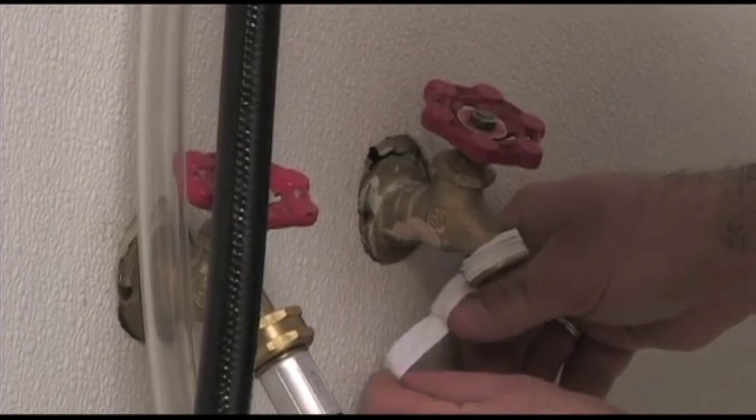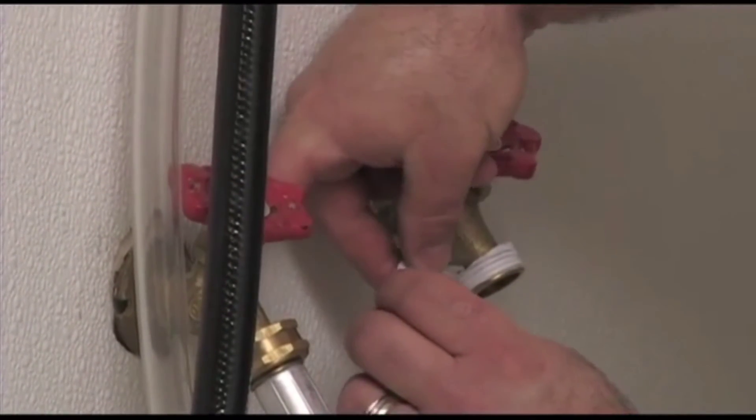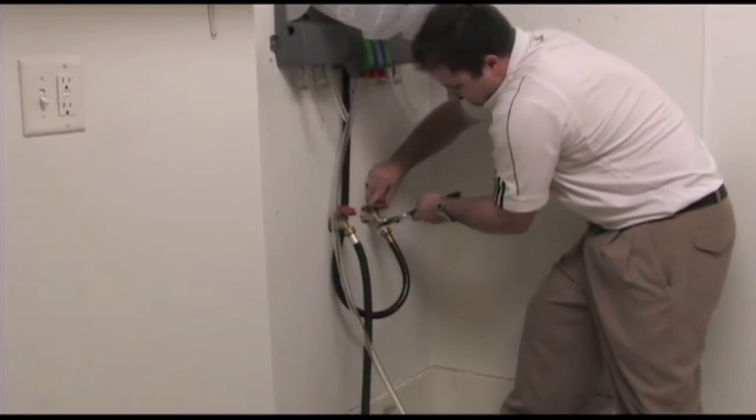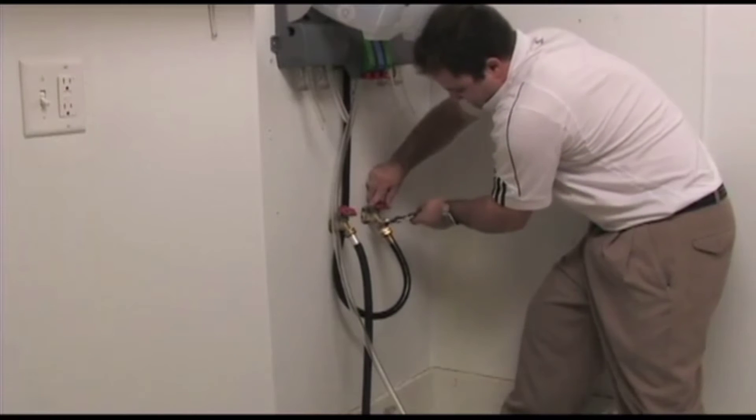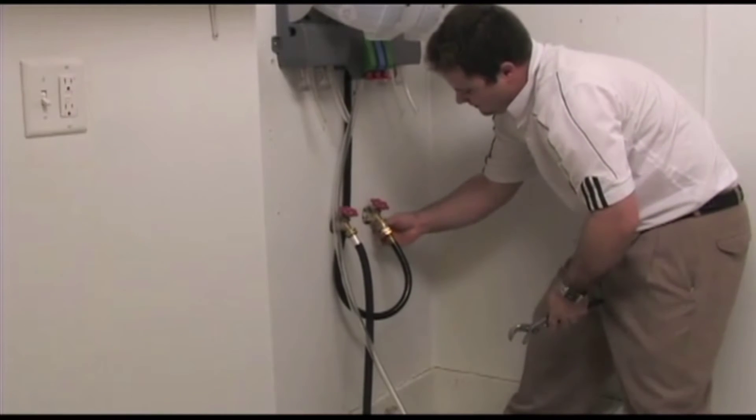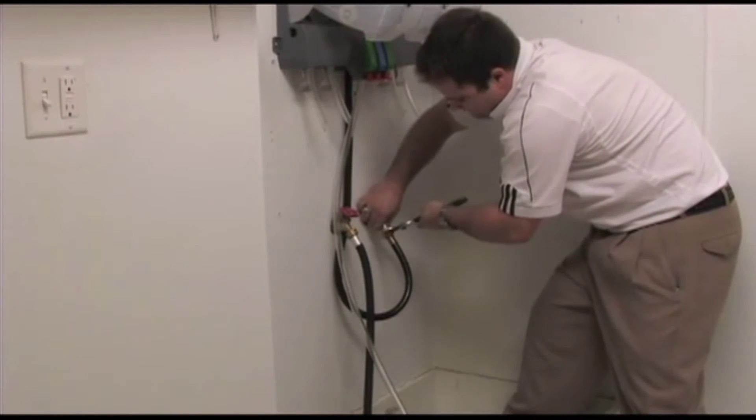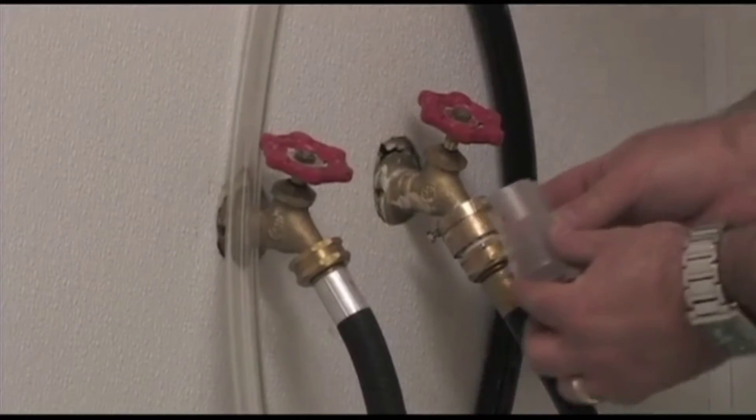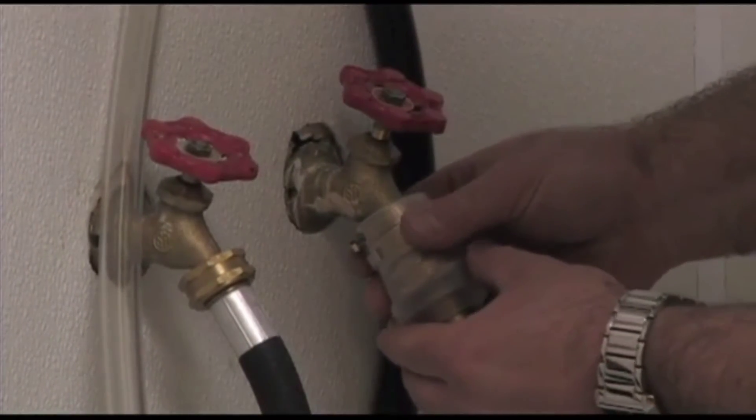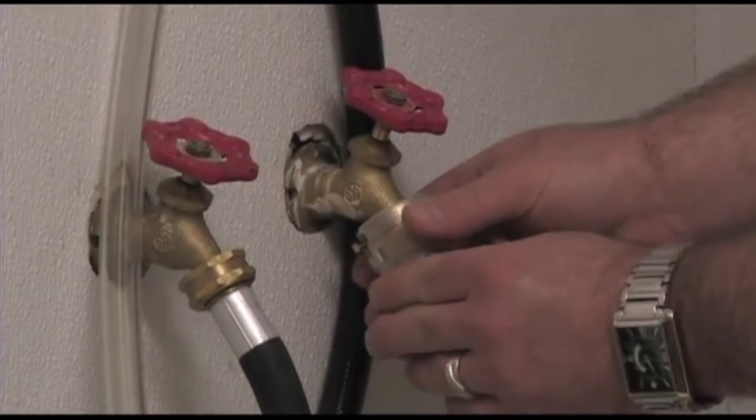Apply Teflon plumber's tape to the water source. Connect the water supply line to the water source. A vacuum breaker backflow preventer is attached to the water supply hose. Snap the plastic shroud found in the parts bag around the vacuum breaker backflow preventer.